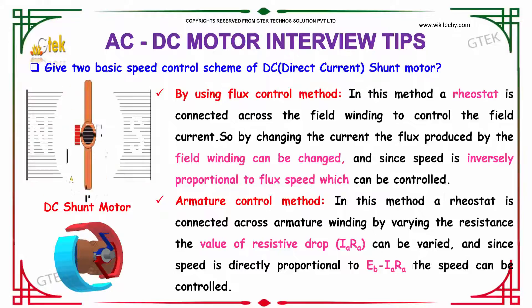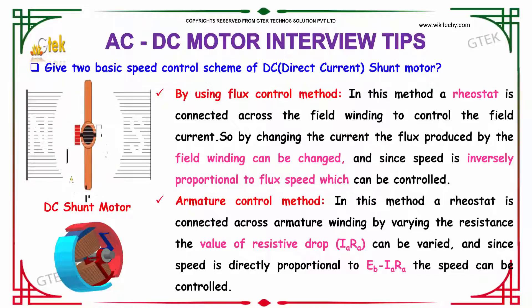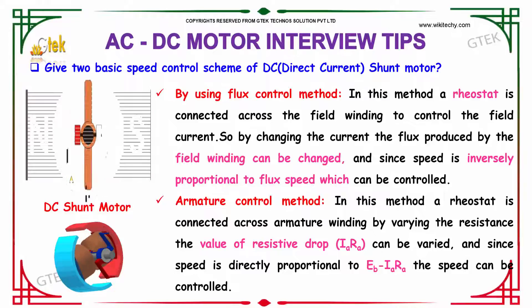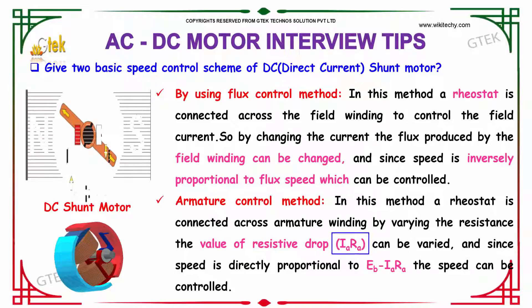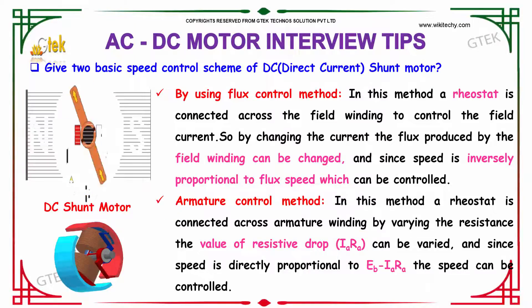The second basic speed control scheme is the armature control method. In this method, a rheostat is connected across the armature winding. By varying the resistance, the value of the resistive drop IA into RA can be varied, and since the speed is directly proportional to EB minus IA into RA, the speed can be controlled.